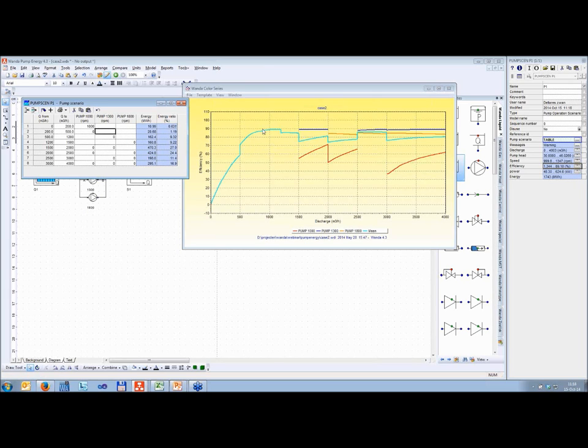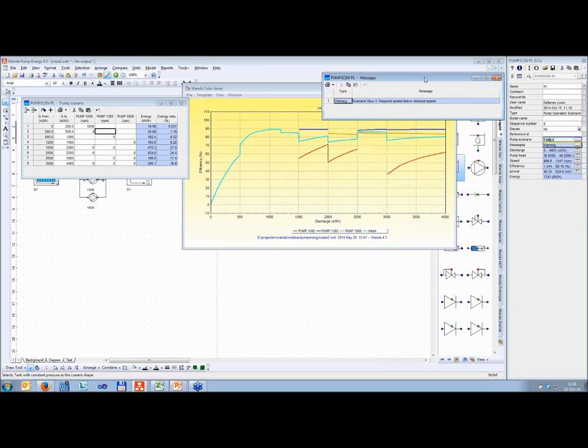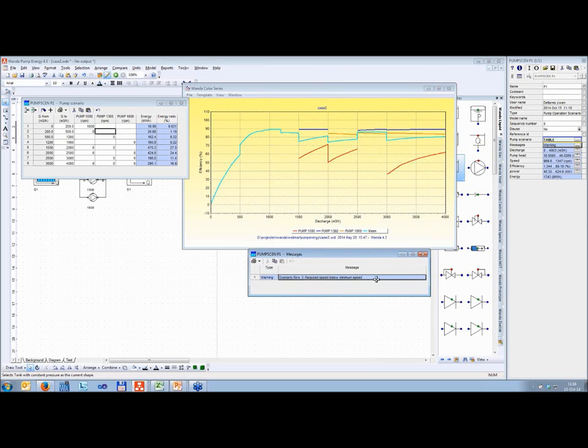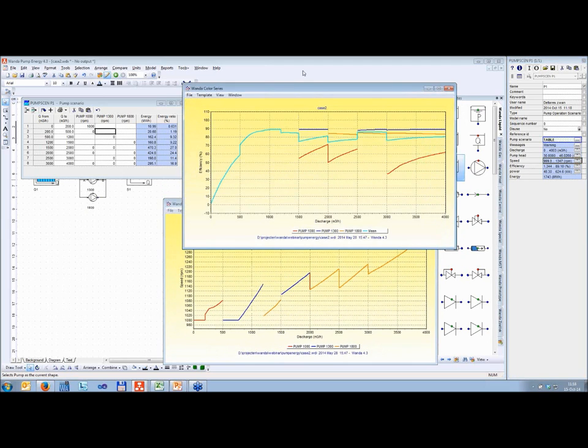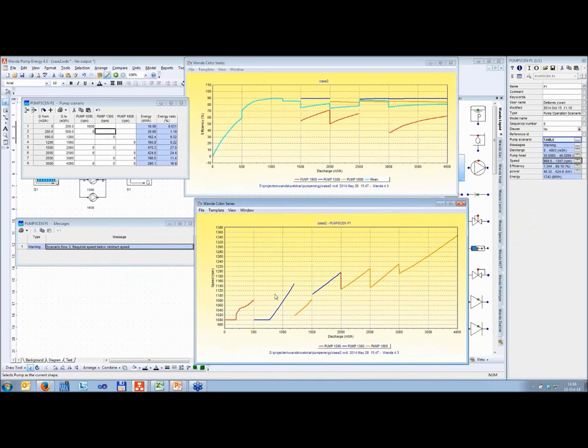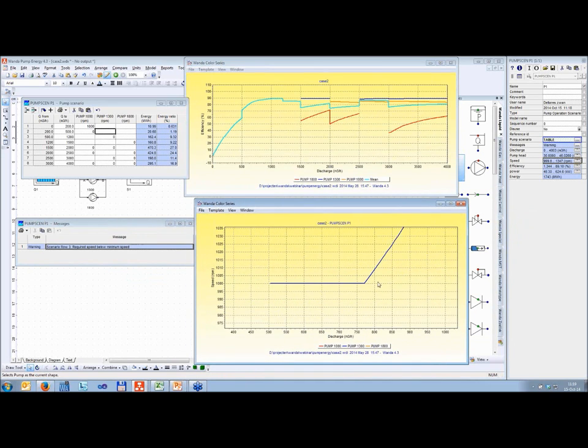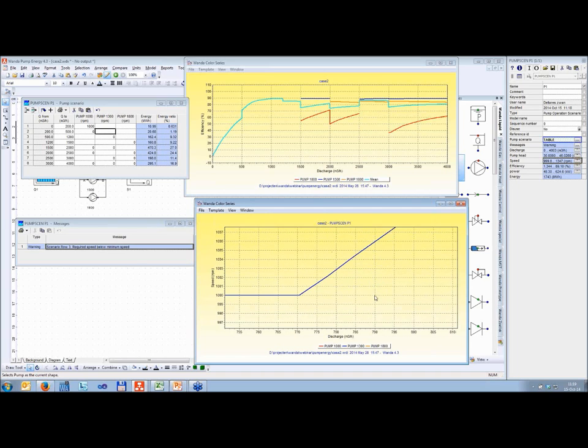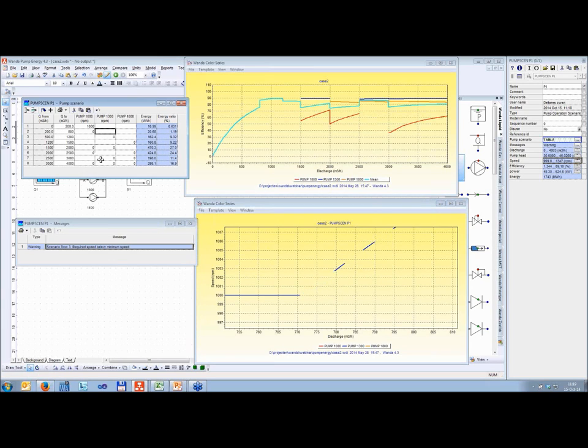Let's switch the second pump on a little bit sooner — make this 500. We have some changes, but we also have a warning which is important to look at. Opening the information, you can see in scenario row 3: 'required speed below minimum speed.' That means it has to run at a speed below the minimum speed specified for the pump. Zooming in, we can see this speed would be below the minimum speed. So the 800 was an okay estimate to switch over — we cannot shift it further. We have to put that back; otherwise it's not a feasible operating point.